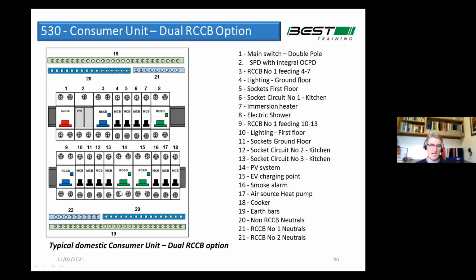Then you need one for your EV charger, and that may be a type A or a type B, depending on the charging arrangements you go for. And then if you have a PV system, and of course we're trying, in Ireland, to achieve 70% of our electricity from renewables by 2030, a tall order, and we're making great inroads with wind, but we need to do a lot more. So we need to have a lot more PV panels on all the new houses and the existing housing stock. If you put a PV system on, it's deemed to be a micro generator, and that has to connect in via its own dedicated RCBO. So that's another RCBO. So what I'm showing here is not really too far off the mark of the way the modern consumer unit is going to look.